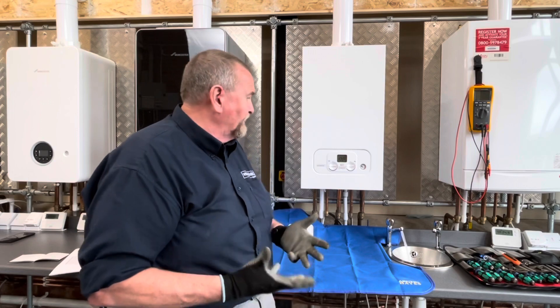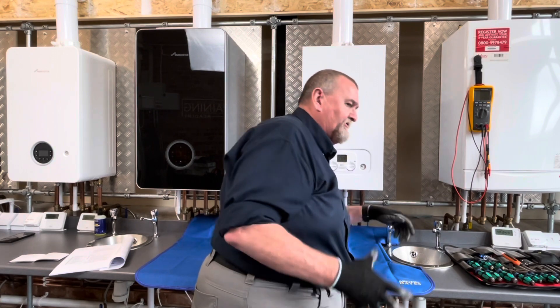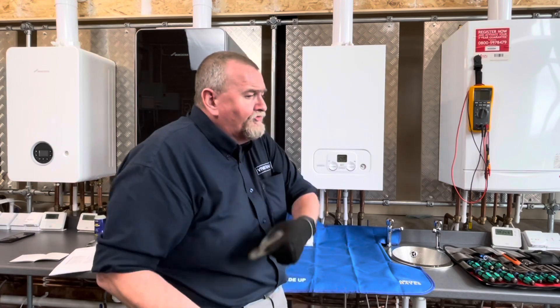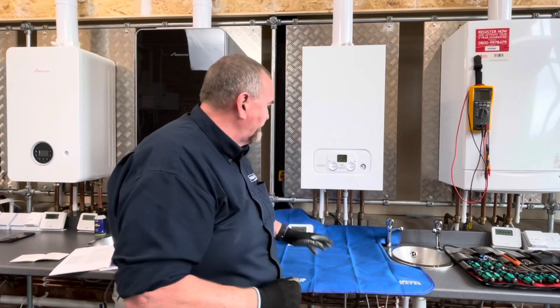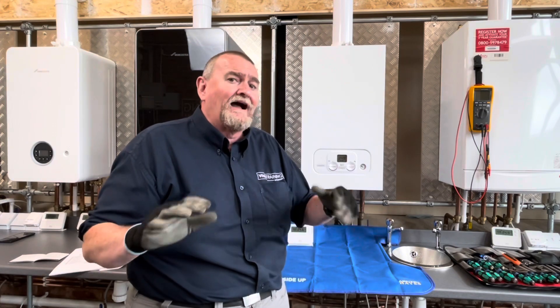What do we do - do we wait, do we carry on? 90% of engineers I come across at this stage would go, 'well it's not lighting so I'm going to turn off and start looking at the gas side of it, start making sure because it's not going to light.' It takes five attempts to light. Now just to go back a little step - it's all about health and safety. So we're in the academy, so I know for a fact if I turn the power off and put the fuse - safe isolation - I know it's killed all the power.